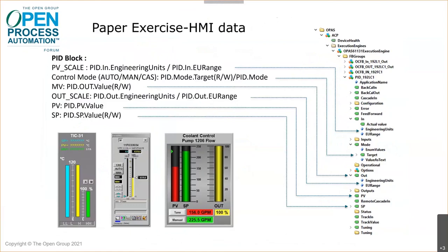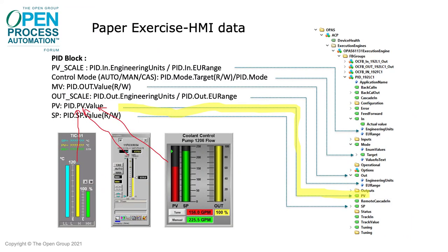HMI graphics can be linked to the OPC UA information model. Note that HMI is not standardized, so the presentation can be vendor-specific, but the layout of the data on the network is standardized, and the HMI or any other application can access it, subject to security authorization. Here you can see the mapping of one of the graphic objects for the PV, and where that comes out of the OPC information model on the right.